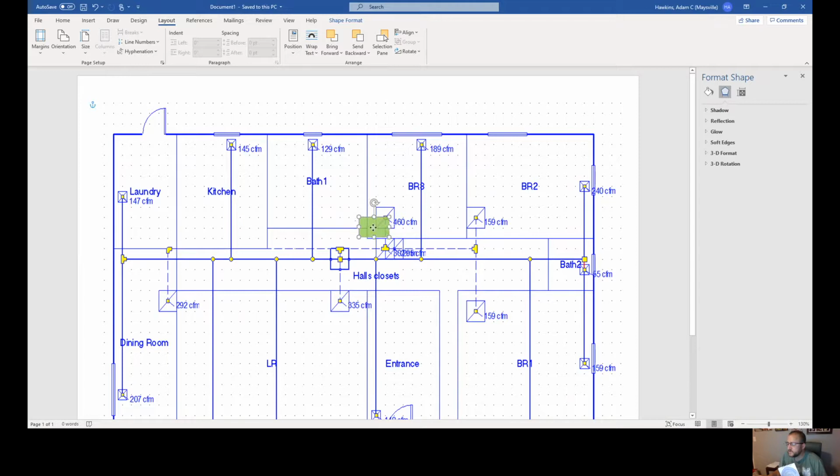All right, so most of the time your duct is going to come in 4 feet lengths. So each piece of duct is going to take up 4 feet. Now, you could do this different ways, but the ideal way is that your air handler would be as close to the center of the house as you can. That way you're dividing up the most of that air both directions as possible.